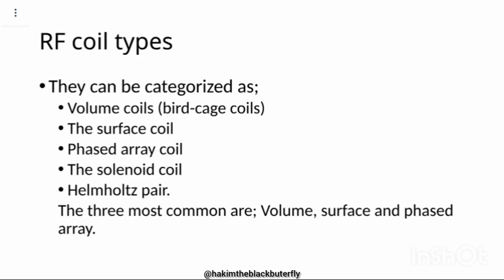So we have types. We have the volume coils, or what we call the birdcage coils, because they are designed in such a way that they cover a particular area. We have the surface coil, phased coil, the solenoid coil, and the Helmholtz pair, but the most common ones are the volume, surface, and phased, so I'm going to talk about only those. I'll ask you to read about the solenoid coil and the Helmholtz pair. The Helmholtz pair are like the gradient coils. You saw how I was explaining the gradient coils within the z-axis; that's how these RF coils are also arranged. So you can try to read about them.